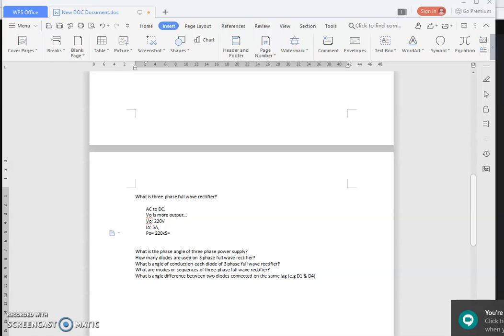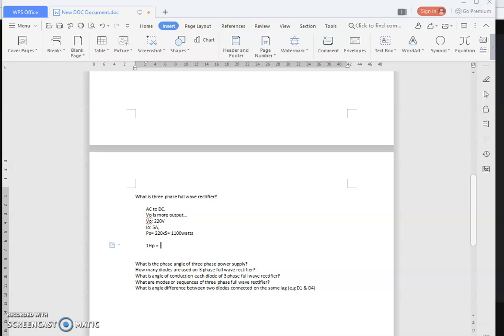220 multiplied by 5 equals 1100 watts. Converting to horsepower: one HP equals 746 watts, so 1100 divided by 746 equals approximately 1.4 HP. In practice, they would roughly say this is a 1.5 HP motor. For these types of high-rating applications, you need to use the three-phase full-wave rectifier.